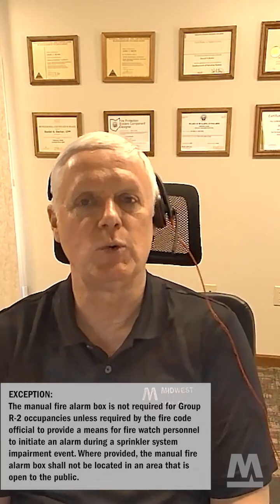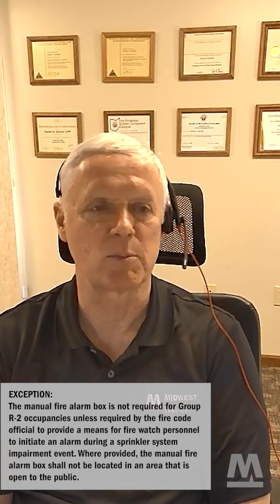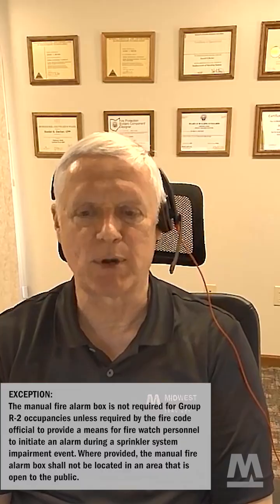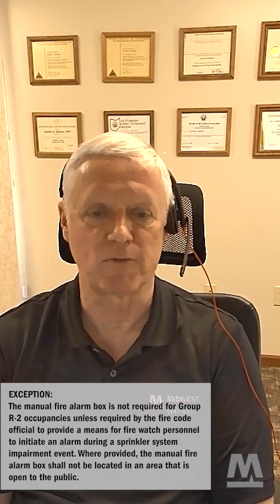There are 2 exceptions to the minimum of one pull station. If you have a dedicated function fire alarm system where you're just operating an elevator, no manual pull station is required. And if you've got an R2 occupancy, an apartment occupancy, a pull station is not required unless the fire code official says it's needed for a fire watch.